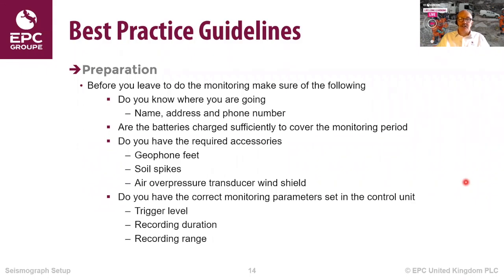Then we need to make sure that we've set up the correct monitoring parameters in the control unit. Much better to do that in the office than wait until you're out in the field. So we're thinking of trigger level, recording duration and recording range. More of those in a minute.